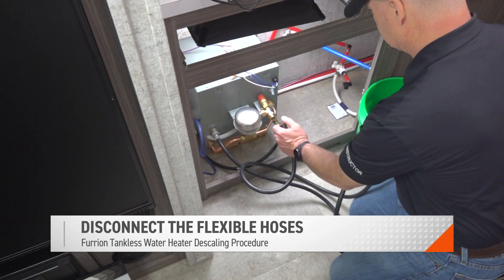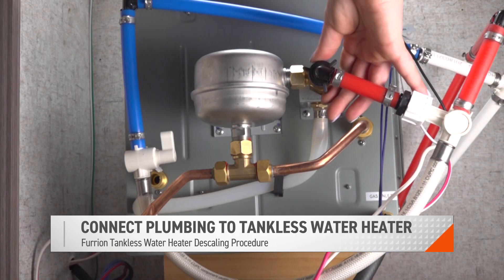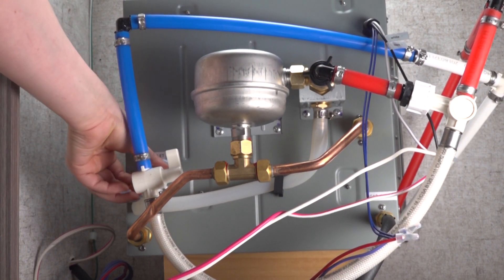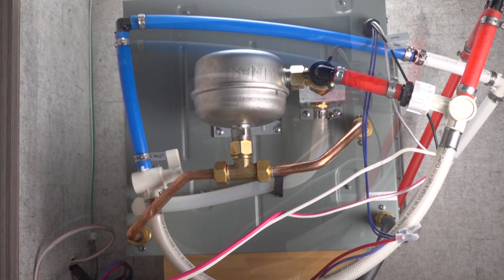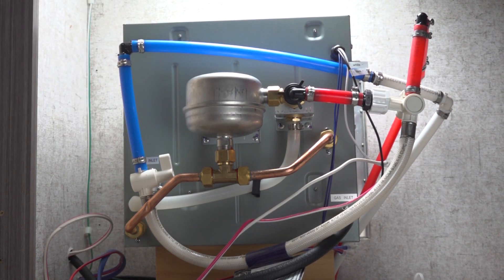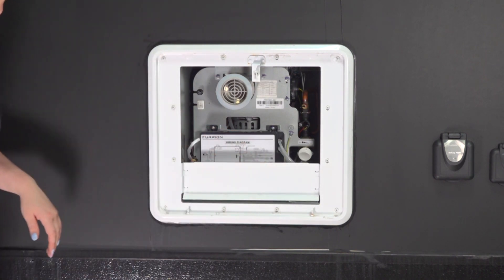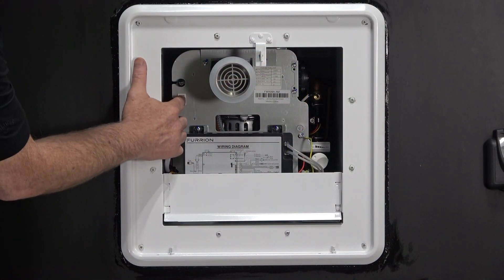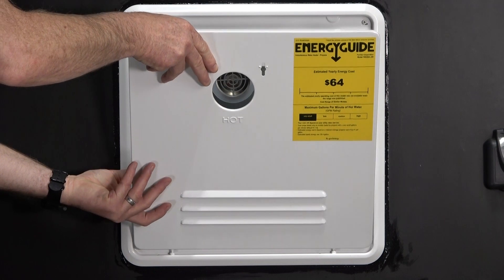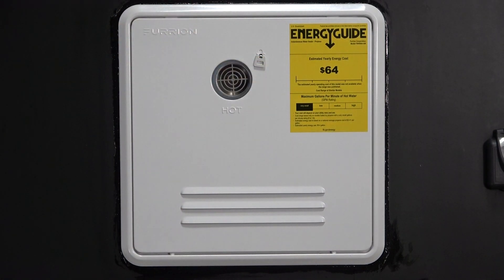Disconnect the flexible hoses. Reinstall the water lines to your cold water inlet and hot water outlet of your water heater. Do not over-tighten or cross-thread your connections, as this can lead to water leakage. Once secure, you can reopen their valves. You can now reopen the gas valve. From the unit's exterior, replace the baffle to the door housing assembly, then power the unit back on. Install the door to the door housing assembly and latch it closed to complete the descaling procedure for the Furrion tankless water heater.